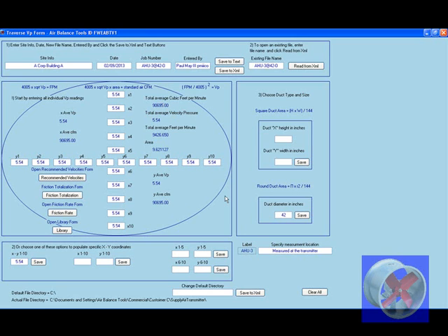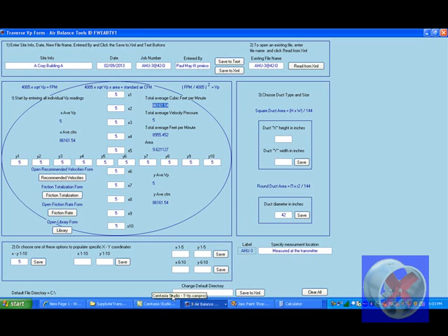Now, if we had a Veris transmitter and it was 5 inches, a Veris transmitter can be scaled for 2, 3, 5, multiple ranges. So if we had a Veris transmitter set up as a 4 to 20 and we had it set at 5 inches and it was a 42-inch diameter, we would have to scale the input that the transmitter is feeding into at 86,161 cubic feet per minute.